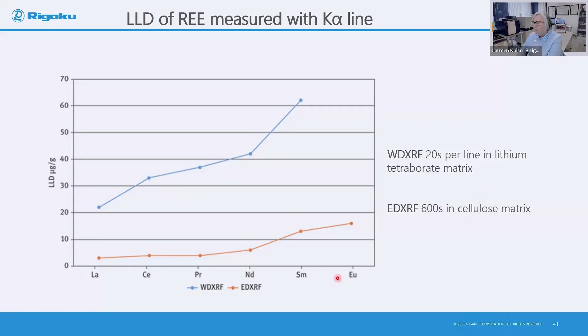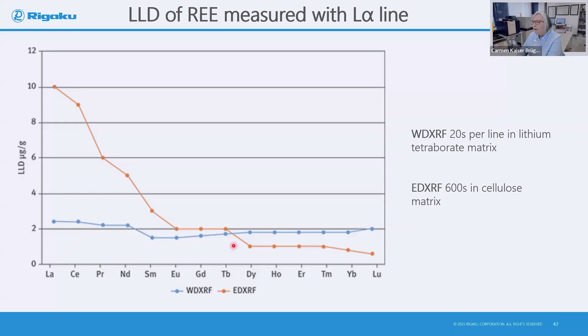Here's another example, but now using the L lines, okay? The first was the K lines, and now you can see the L lines. So you can see with the L lines that we get a much better limit of detection for WDXRF in the same matrix with lithium tetraborate as compared to energy dispersive XRF.